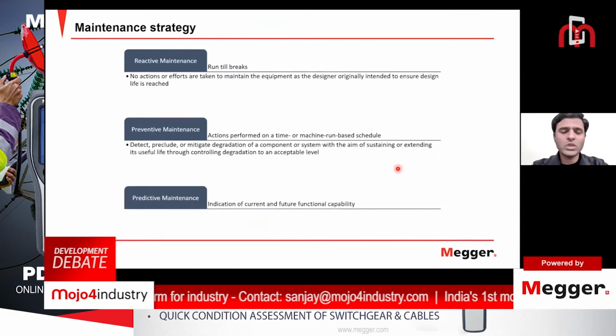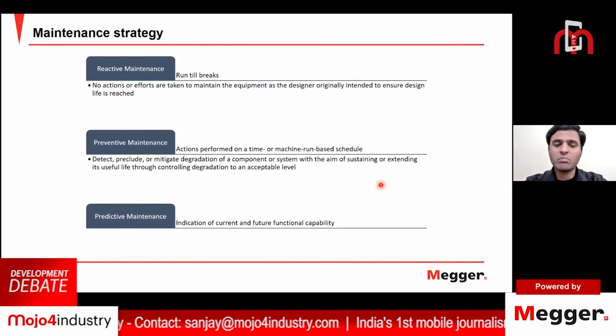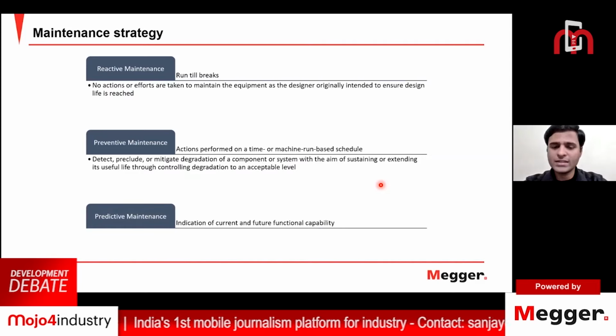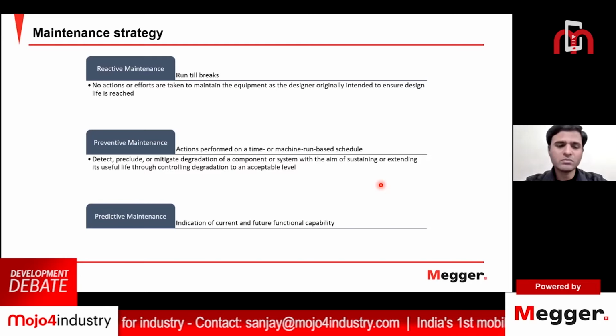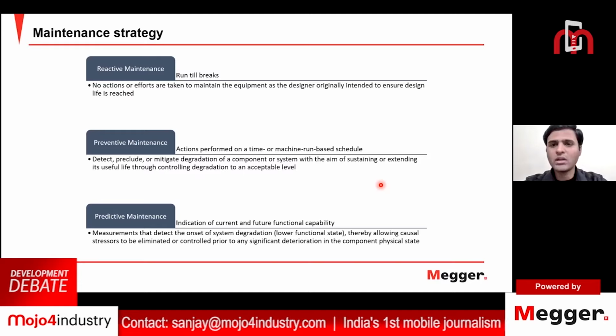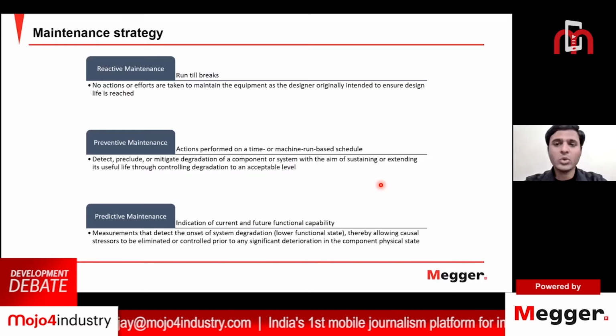The modern maintenance strategy follows prediction-based maintenance, that is condition-based maintenance, which helps us identify the current functional state of the electrical asset and plan preventive maintenance depending upon its current situation. Predictive maintenance can be done in online condition without switching off your electrical asset, because taking a shutdown is a very tough job. It can affect the complete output of the substation or the utility.